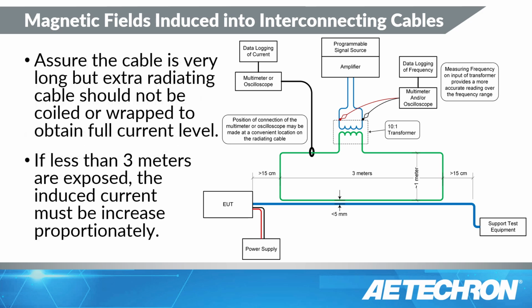And I say that because, remember I was telling you that's a low impedance output on this thing. If you do coil that wire up down here in the corner, you end up creating an inductor, which can change the impedance of your output. And if you've calibrated into a straight wire, or worse, if you calibrate it into a whole coil of wire, and then you go to run the test, you may overtest.